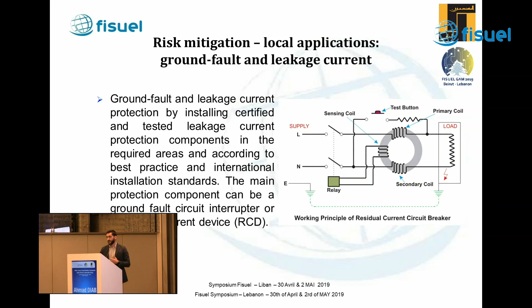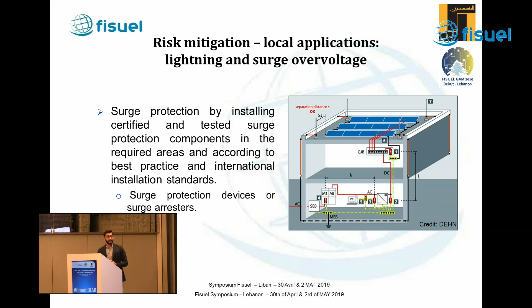For lightning and surge over-voltage protection, there's the surge arrestor devices, selected with the correct type: type 1, 2, or 3. Also, considerations for the type of installation, the roof type (metallic, flat, or concrete), and whether the roof has an existing lightning protection system, including the required separation distances between the mounting structure itself and the LPS.